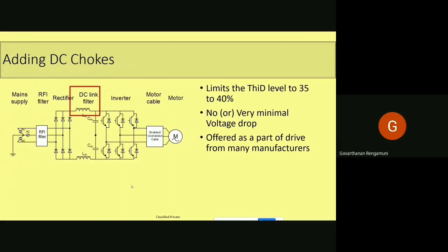The first one is adding DC chokes. You have seen in the earlier part how the current got polluted because of the DC capacitor. The DC capacitor makes the grid current very poor. So by adding a filter like this in the DC link, which is an inductor, the THD level can be reduced. Then the current will be reconstructed to a somewhat better level. By doing this DC choke connection, we can limit the THD level to 35 to 40%.